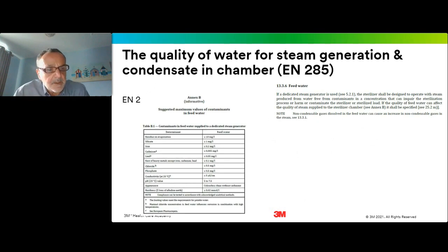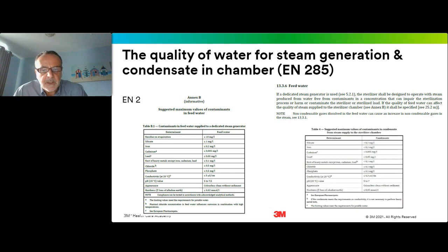So if we look in EN285, and I'm sure in AAMI TIR standards, there are requirements for the contamination levels present in the boiler feed water, and you can see this on the left-hand table. And then also, if you were to collect some condensate from the steam, then again, there are limiting values for the chemical contamination in those samples. So again, if you look in this left-hand table, you can see that the contamination levels recommended are very, very low. We're talking about, for example, in lead, 0.05 milligrams per litre, hardness values of less than 0.02 millimole per litre, and then for the condensed steam, very similar levels. Some of them are even lower.